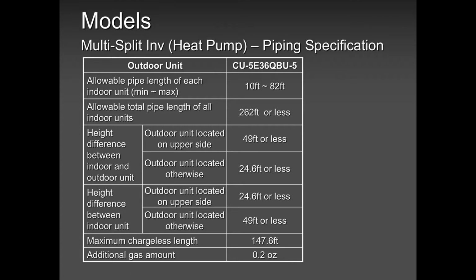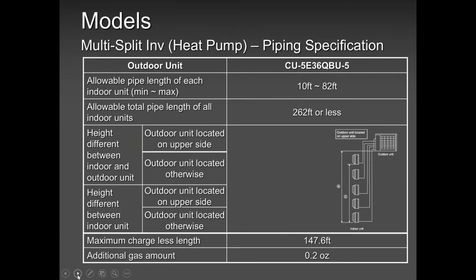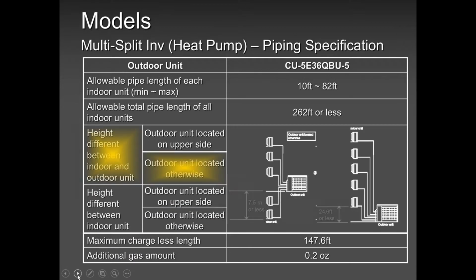Okay, so in this case, you need to add refrigerant after 147 feet, and you should never go above 262 feet, and you should never go above 82 feet per indoor unit. Those are the slides that are showing you up and down, when the outer unit is on top, when the outer unit is in the middle, when the outer unit is at the bottom.